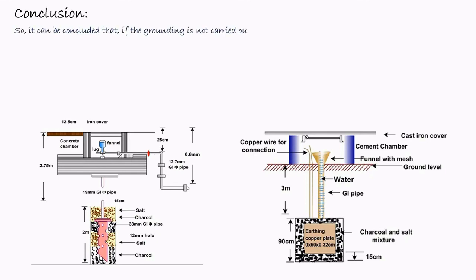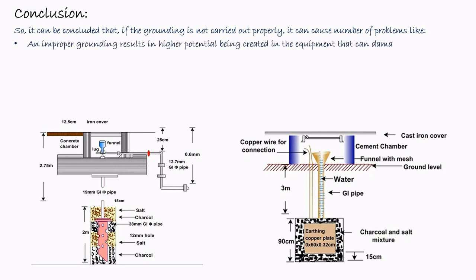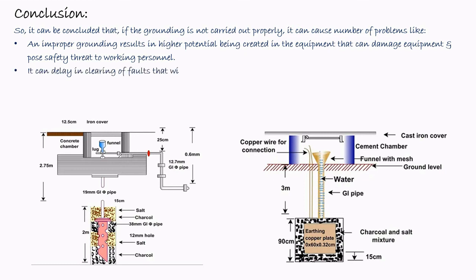Therefore, it can be concluded that if the grounding is not carried out properly, it can cause a number of problems. Improper grounding results in high potential being created in the equipment, and that can damage the equipment and also pose a safety threat to working personnel. It can delay the clearing of a fault, resulting in insufficient current flow. So if the grounding is not proper, the fault will not be cleared in time. Therefore, the system will be delayed in restoring, and the current flow will also be changed.